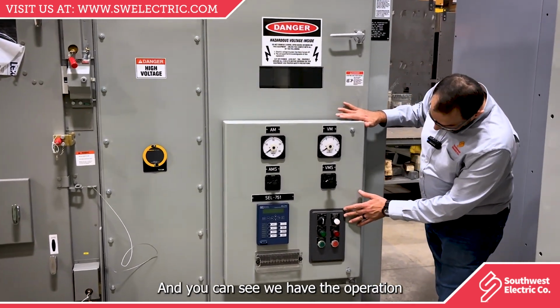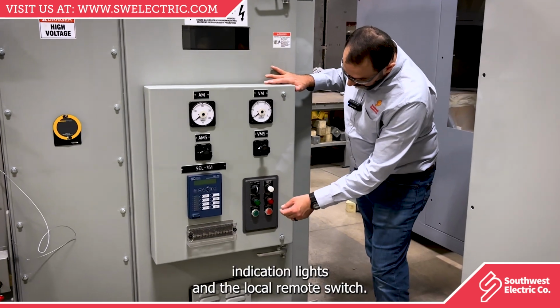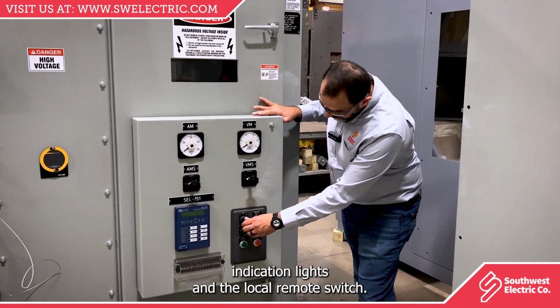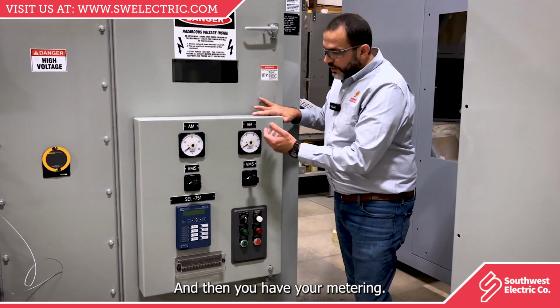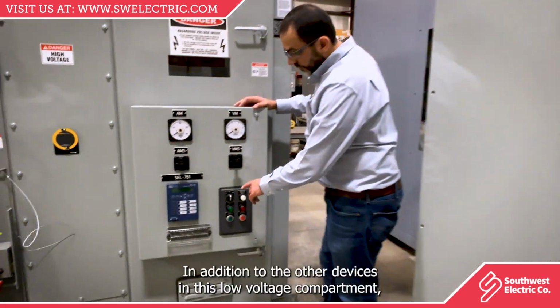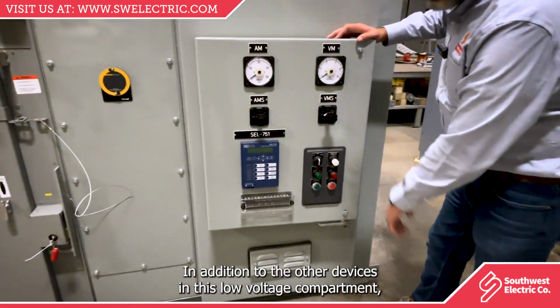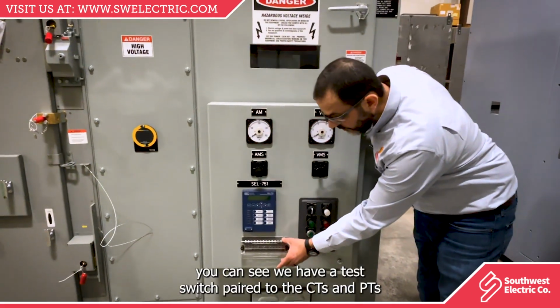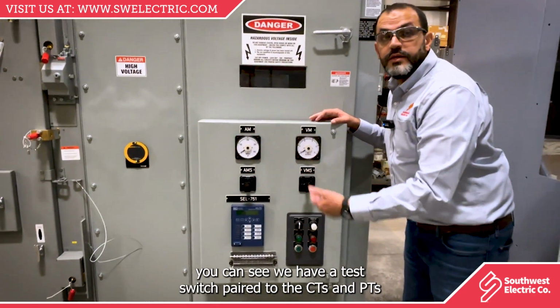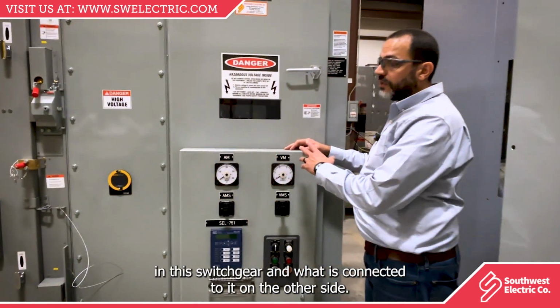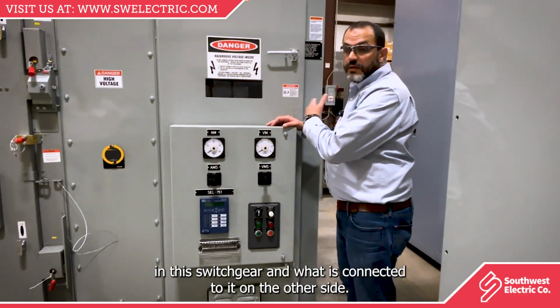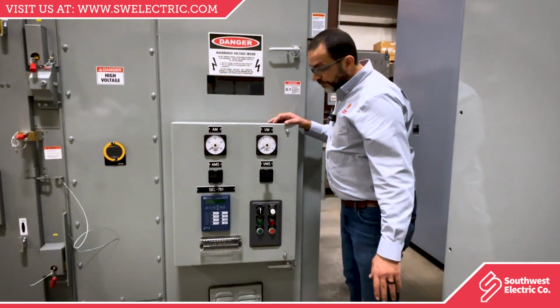You can see we have the operation indication lights and the local remote switch, and then you have your metering. In addition to the other devices in this low voltage compartment, you can see we have a test switch paired to the CTs and PTs in this switchgear, and what is connected to it on the other side.